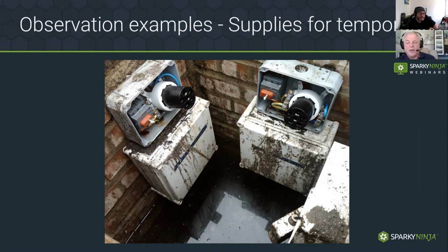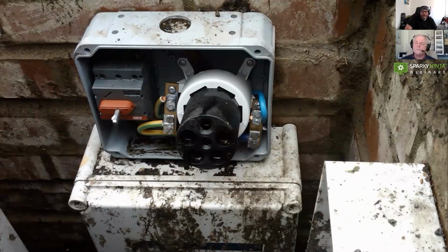It's the wrong IP code for that environment anyway, because if it fills up and water comes over the top, it needs a much higher rating. We need IP67 rather than IP65, and that should include the bottom enclosure as well as the top. It's no good having the top enclosure IP65 and the bottom IP44 - water goes in the bottom enclosure, comes up through, and fills the thing up. So that was the issue with that one.